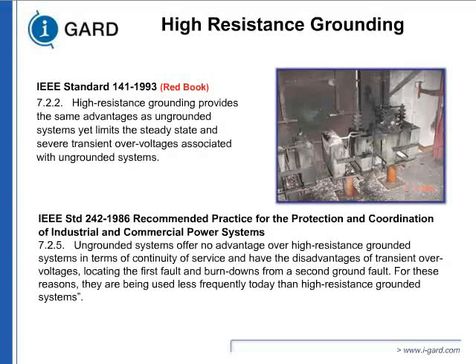IEEE Standard 242, which is the Buff Book, in 1986 mentioned the same thing. And you look, their wording was different. That's a coordination standard, saying an ungrounded system offered no advantage over high-resistor grounded. The Red Book was saying high-resistor grounding is better. The Buff Book says it in a different way. And if you notice, the Buff Book is telling you that the disadvantage of transient overvoltage still stays with the ungrounded system. High-resistor grounding limits that, gives you the ability to locate the first fault, and minimizes burn down. Even on the second fault, you won't have a burn down because it will trip some overcurrent device. Okay? And that's the reason the Buff Book in 1986 recommended it. For these reasons, ungrounded systems are being used less frequently than high-resistor grounded systems.